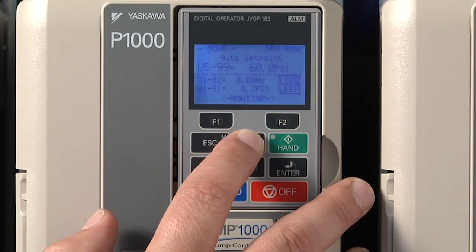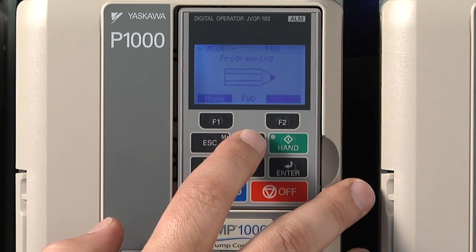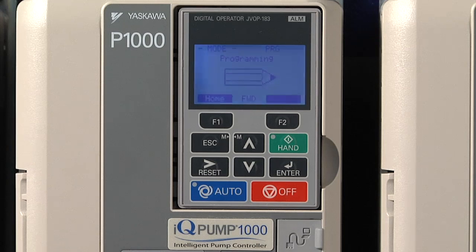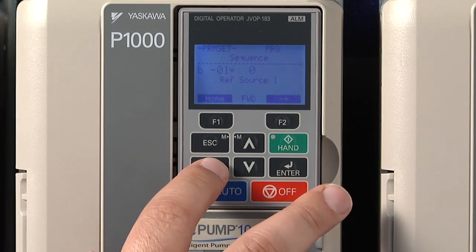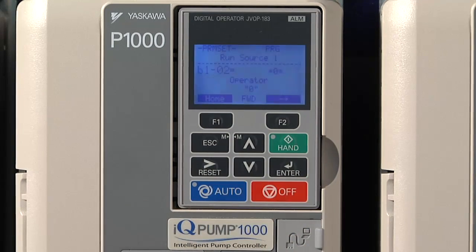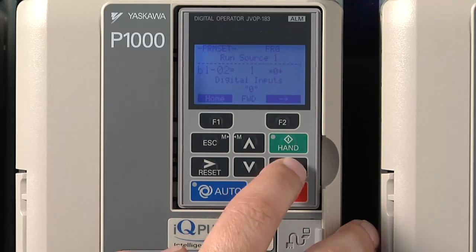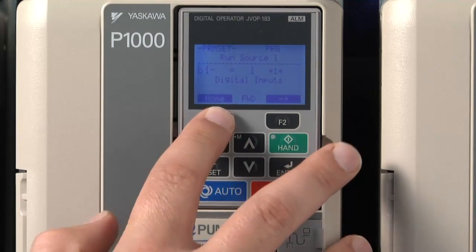From the main menu, press the up arrow until you reach the programming menu — the one with the image of the pencil. Enter the programming menu, then scroll to parameter b1-02. Select by pressing enter, then change parameter b1-02 to 1 for digital input. Press enter one last time to finalize the change. Now you're done setting this parameter, so press the F1 button to return to the home screen.